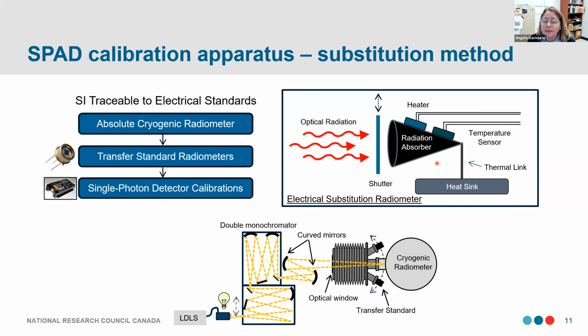If we close the light, then we have this heater that applies the same amount of heat, which is an electrical substitution technique. So here we can actually go up our calibration chain, and we're traceable to our SI system of units this way. Here's another cartoon of our setup at NRC, where we have broadband light sources, a double monochromator system that gives us a single optical path. And we have our cryogenic radiometer in our system here.